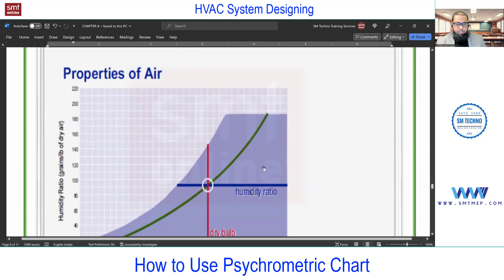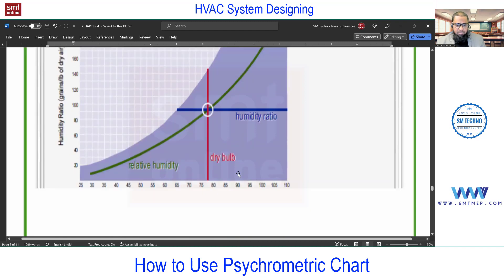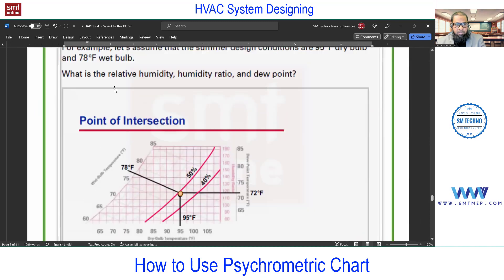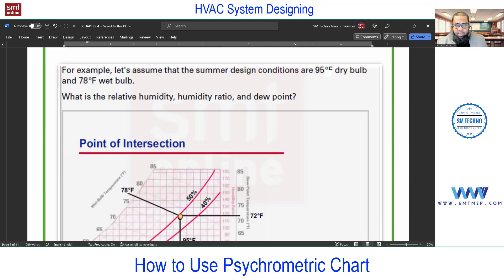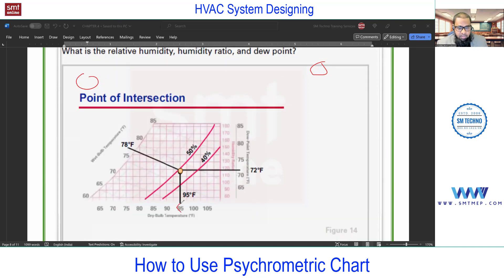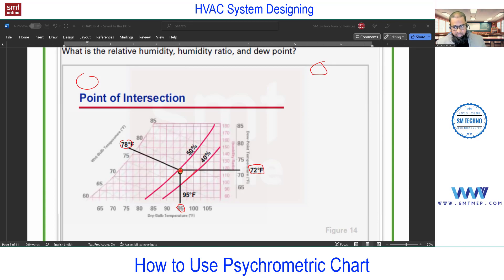Now we'll do one simple example using the psychrometric chart, taken from Trane. In this example, the two known properties given are 95°F dry bulb and 78°F wet bulb. Dry bulb uses vertical lines and wet bulb uses inclined lines — intersecting these two gives you the point on the chart. Going horizontally from that point gives the dew point temperature, and the RH line passing close to the point shows approximately 50% RH.